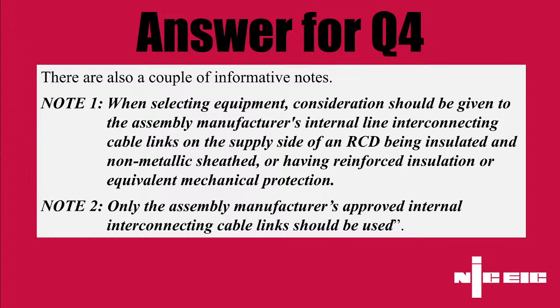Again, if you look at those notes attached to the regulation that we talked about, which is a great regulation because it is one of the longest numbers in the book. One day I'm going to have a look and see if I can find which, because there's probably a part 7 regulation which will break it, because they tend to have the part 1 to 6 reg behind the 7.